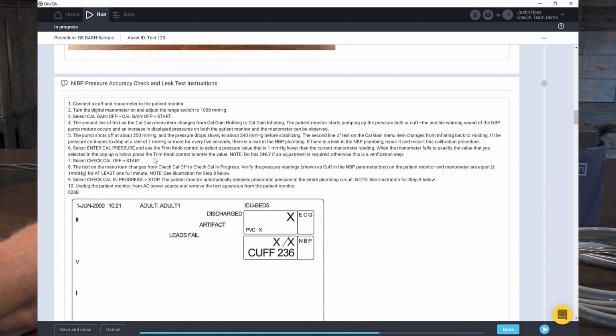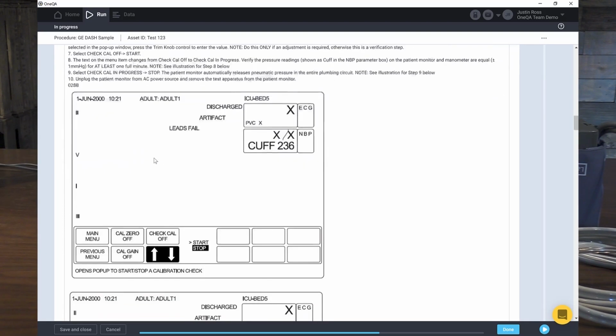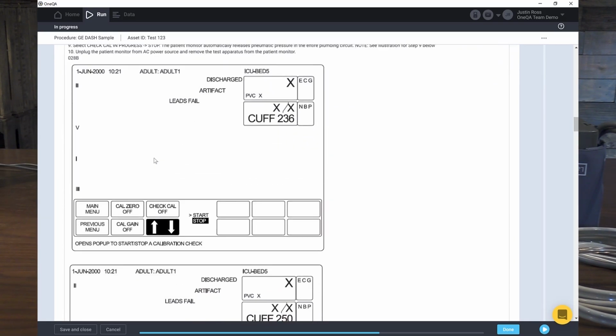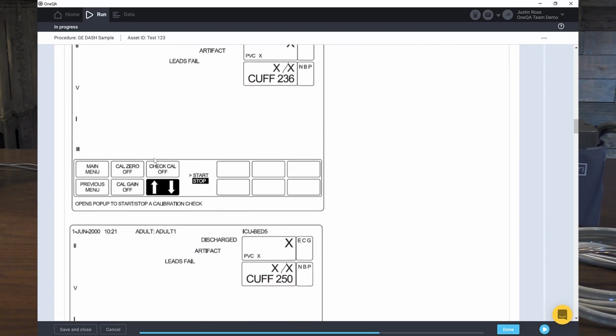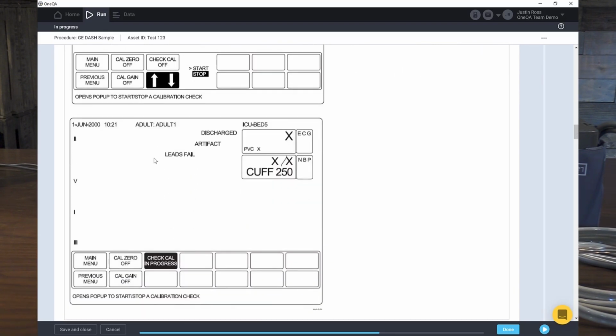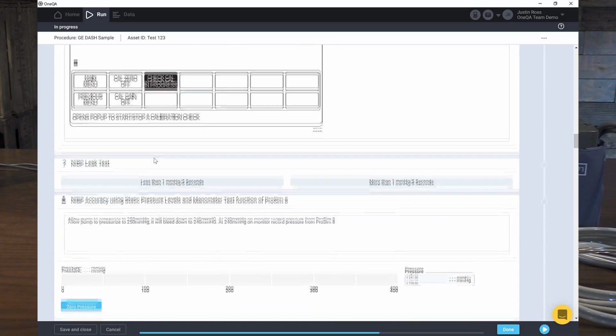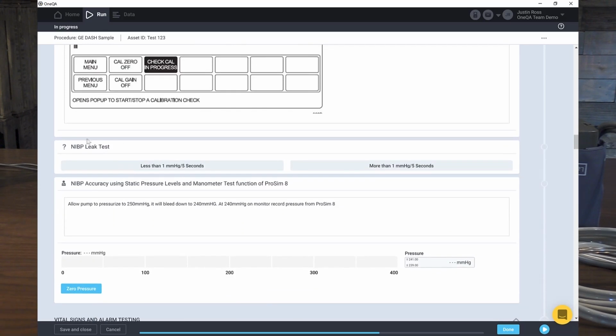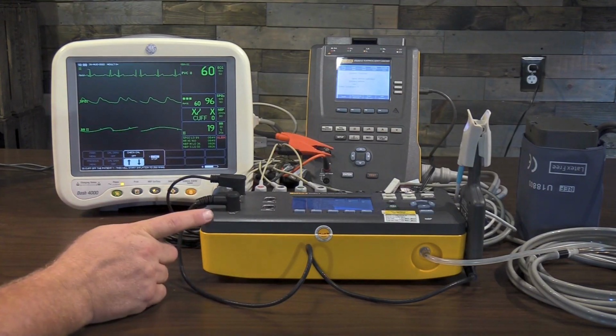We're going to go over here to calibrate and NIBP and cal check. All right. Hold up there for a second. Here's a diagram showing us exactly the keystrokes. We pulled this out of the manual and embedded it, so we have no question about what we need to do. We're actually going to do two tests at once. We're going to do the non-invasive blood pressure leak test as well as the NIBP accuracy test. So let's go ahead and zero our pressure meter, which is built into the ProSim 8.